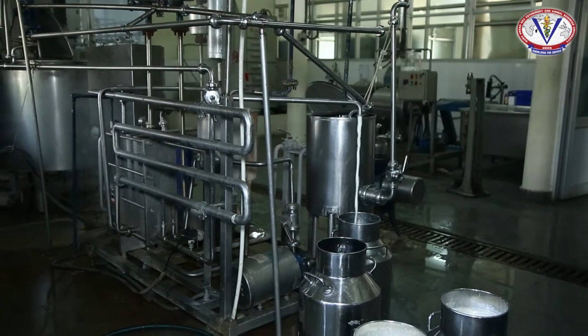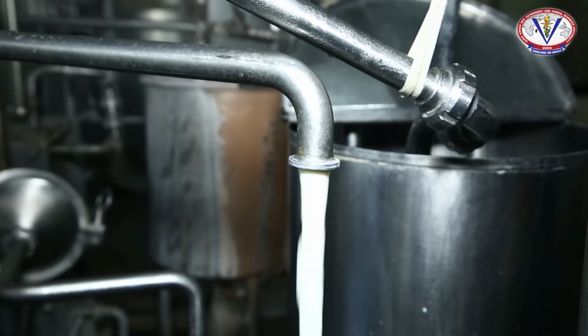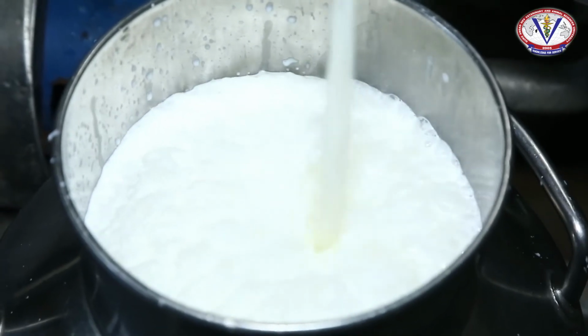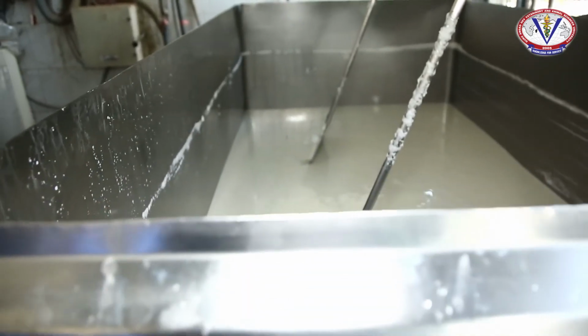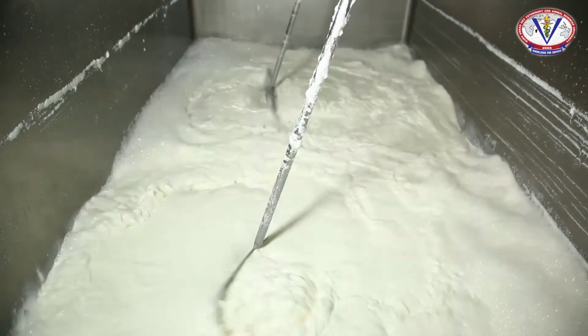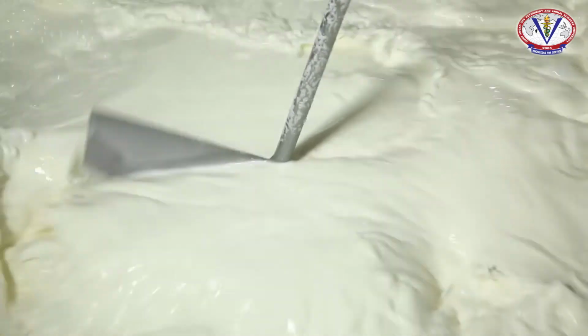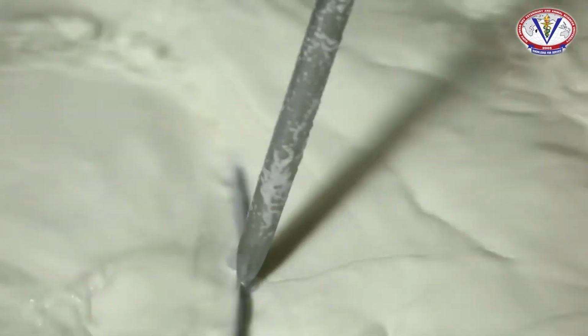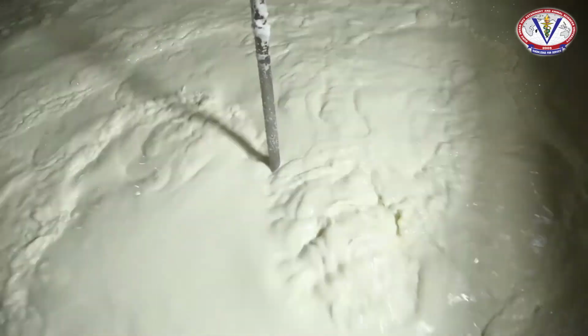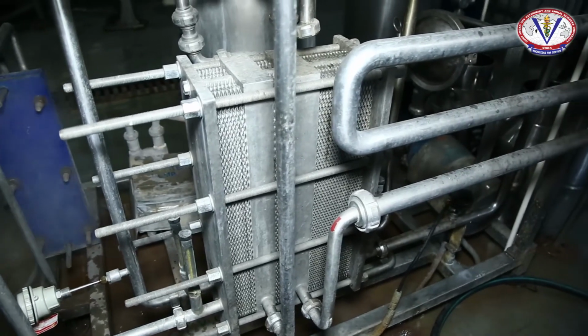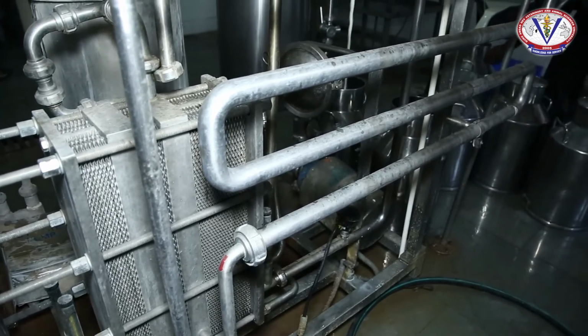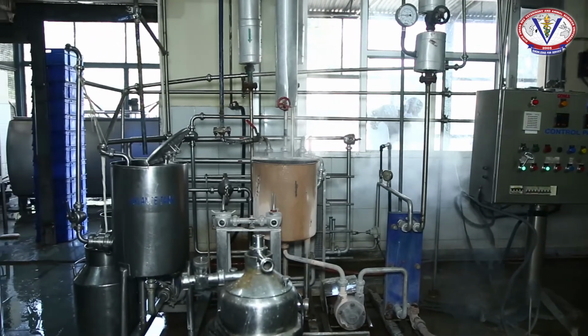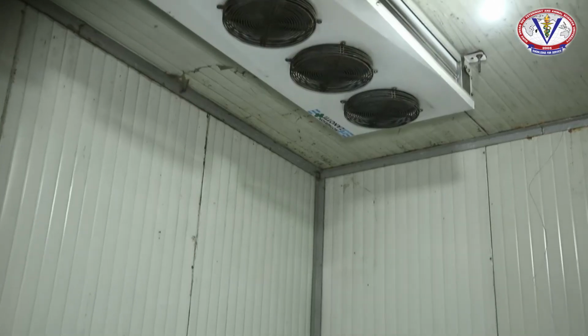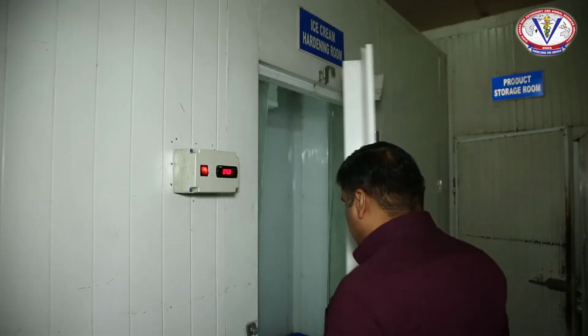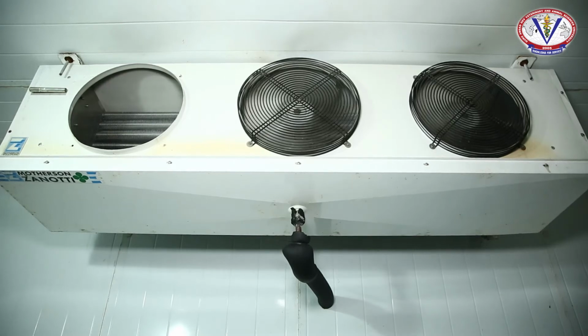The refrigeration systems in the milk industry or the dairy industry are used for cooling milk directly after it leaves the cow and before transport to the central creamery, and it is done by using a component called the BMC, or bulk milk chiller, keeping the raw milk cool after it enters the creamery. Again we are using the BMC, and these systems are used for ice bank systems in large dairy plants where milk is being chilled by heat exchange between the water and the milk, such as in the case of PHE or plate heat exchangers. These systems are also employed for product storage areas such as cold storage, where split type systems are used and the product is being stored.